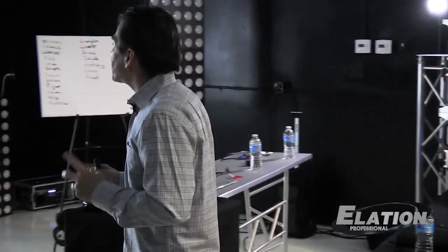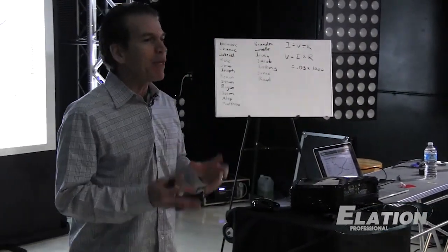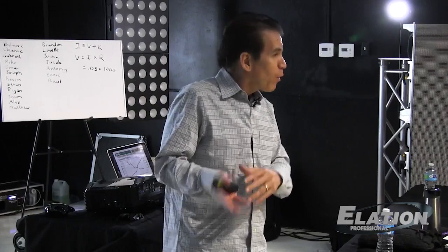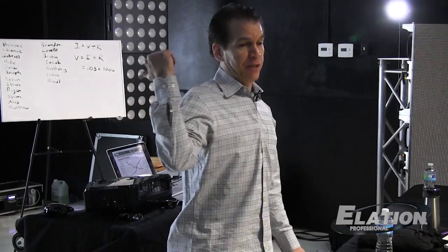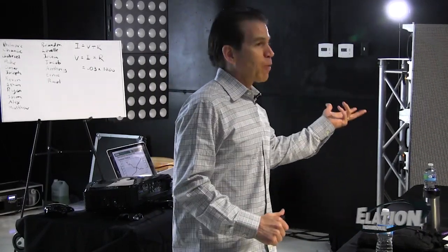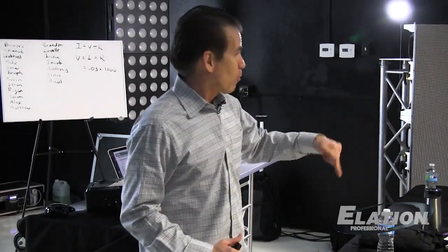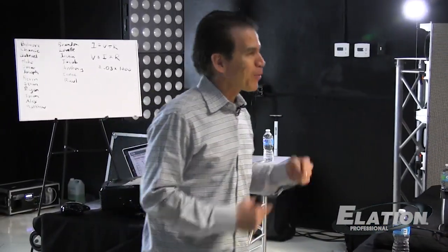There's a standard for the use of GFCIs in the entertainment industry. And basically what it says is that anytime you use electricity in the proximity of water or moisture, you should be on GFCI protection. If there's a possibility that it could rain, and I know it will rain in Southern California because I was here in December and it was raining. I didn't believe it until then, but I saw it with my own eyes. So even though it seldom rains in California, you still need to be on GFCI protection.